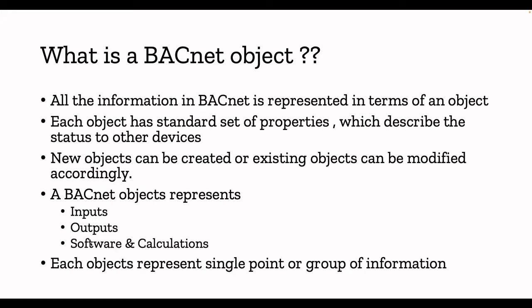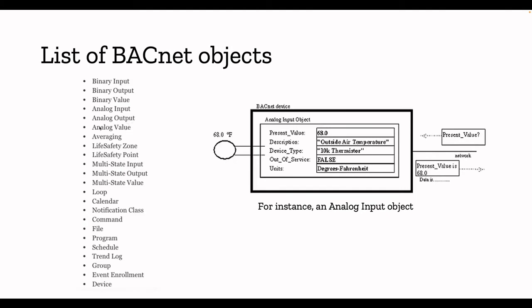New objects can be created or existing objects can be modified according to user needs. Basically, a BACnet object represents inputs, outputs, software, and calculations — all BACnet objects come under these categories. Each object represents a single point or a group of information. There are 23 widely used BACnet objects — it's not limited to 23, there are more, but in today's building automation and control network these 23 are the widely used ones. We will focus more on the analog input object.